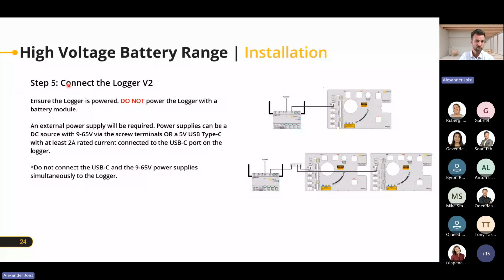Next step is connecting the logger V2. For each high voltage system, unlike the low voltage side, each system must have a logger - that's very important. You can connect it in different ways. On the low voltage side, we often connected the logger directly to the battery as a power source. This time, please don't do that - it's not going to work because the voltage is far too high for the logger.